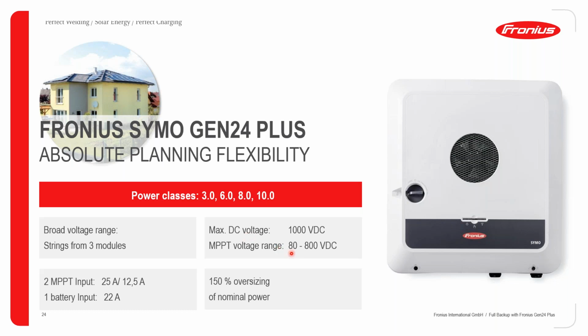And our MPPT voltage range is active between 80 to 800 volts DC. So when you are planning your system, please make sure that you try and plan your strings such that it can fit somewhere in this MPPT voltage range in order to ensure that you get the best system performance.